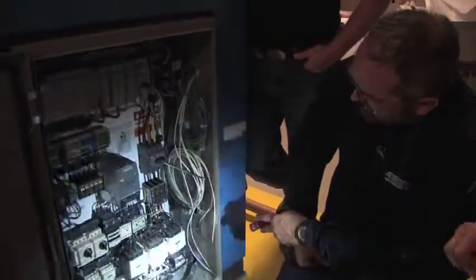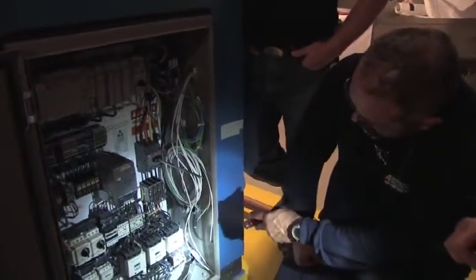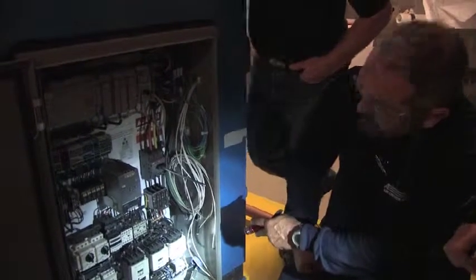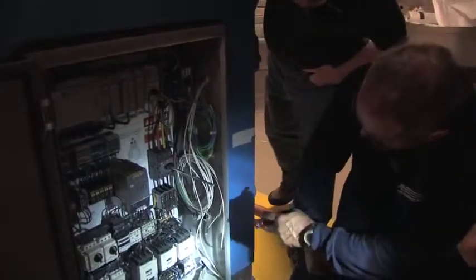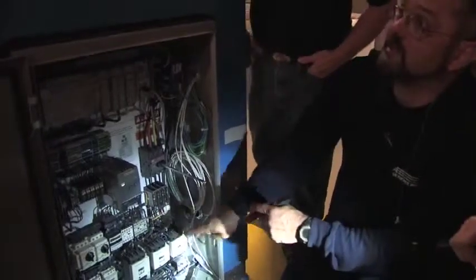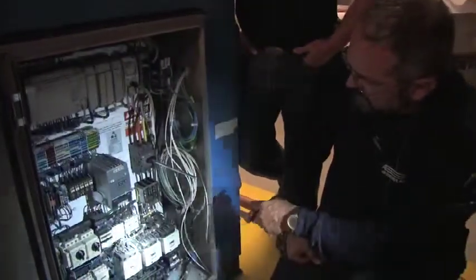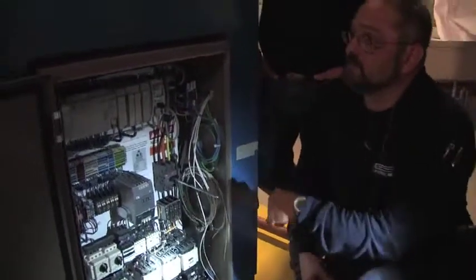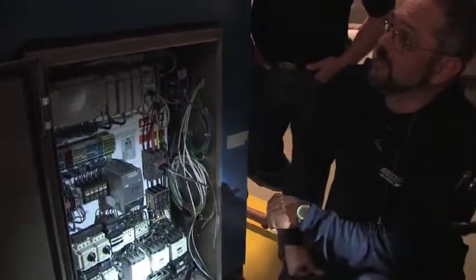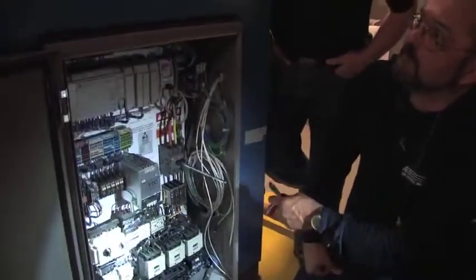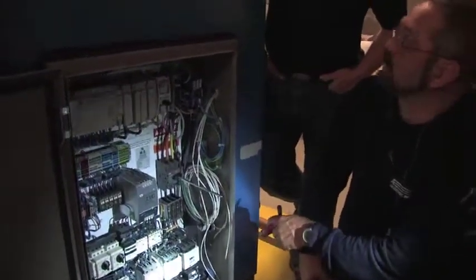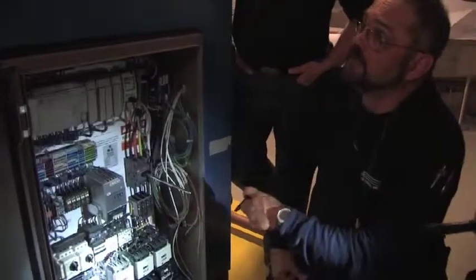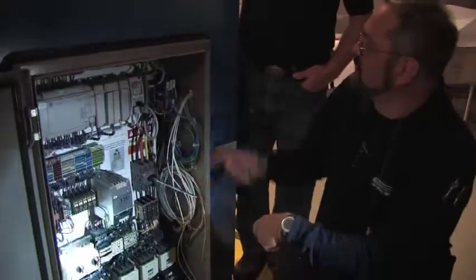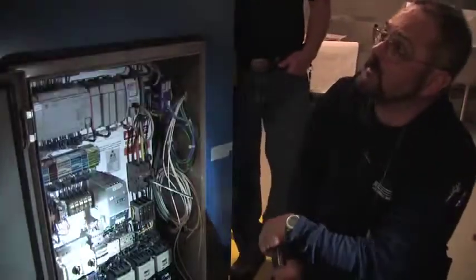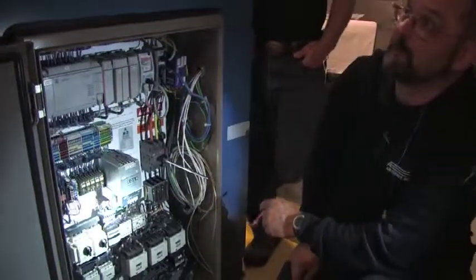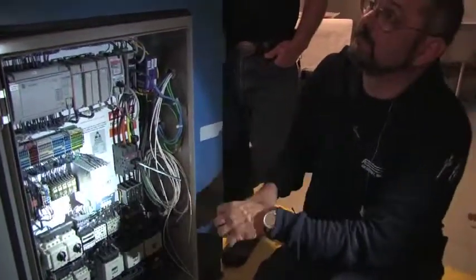Yep. Now the one that isn't is the main motor. That one you clear by hitting that blue button next to the red one. The red one's a test. Okay. Biggest thing to remember about this is it's Y delta. So all 6 leads to the motor are carrying basically half the amperage, but it's not really half. It's 58%. So that overload block needs to be set to 58% of whatever the full load is. I see that a lot. People take the motor nameplate and set it to the full motor nameplate. If you set that overload to full, about the max you want to set it to is 60%.